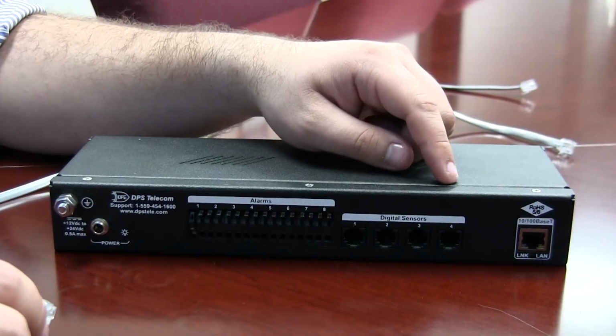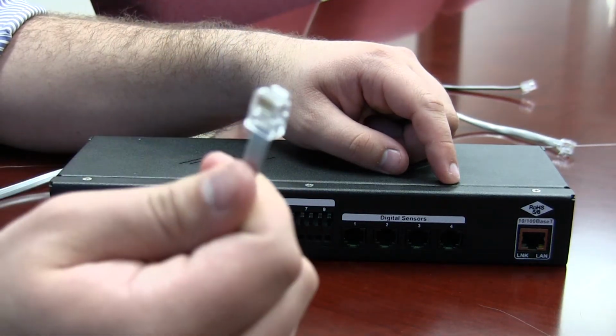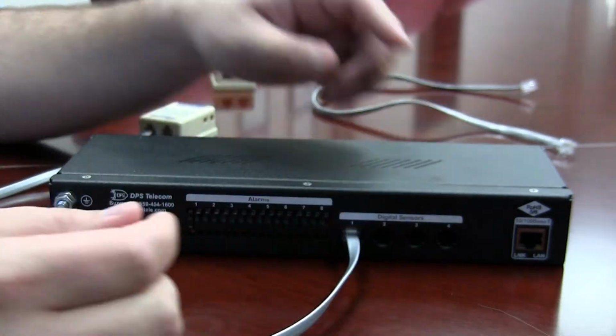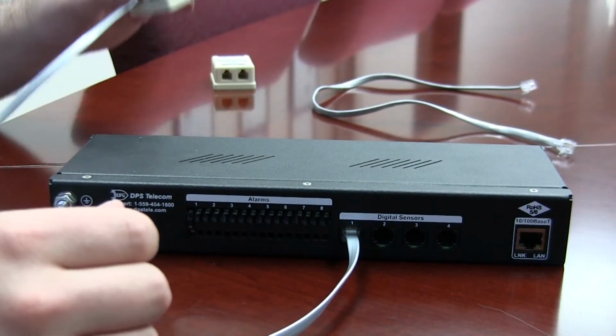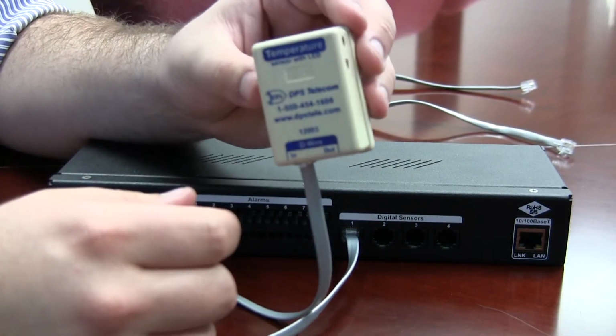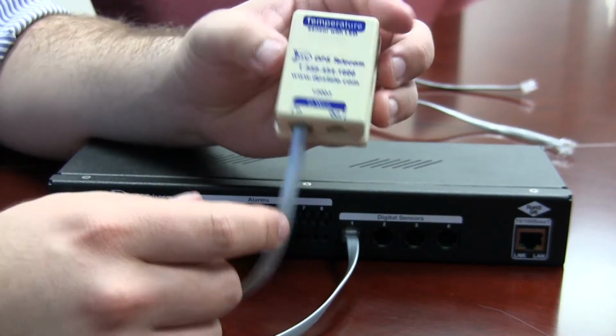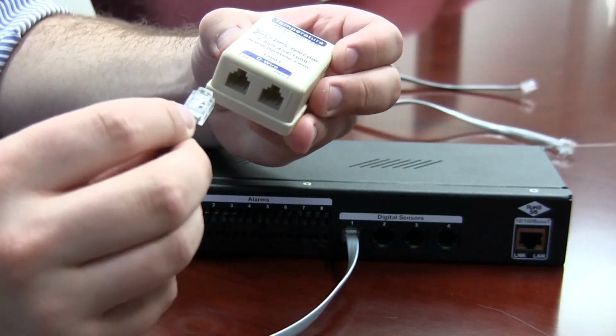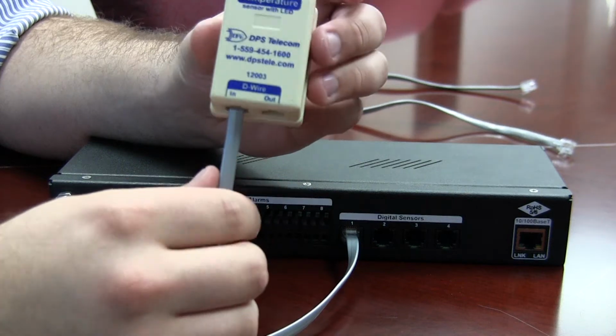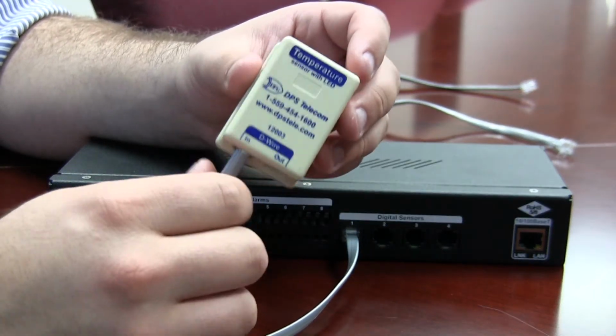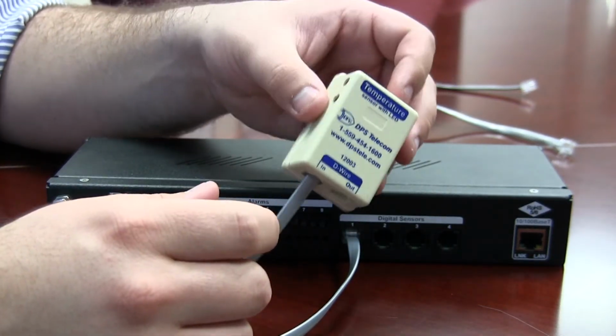To each of the four digital sensor inputs, you'll be able to insert a standard RJ11 cable that clicks in. This cable can be up to several hundred feet long, depending on how many sensors you're going to have in this string. And you're connecting to D-wire sensor nodes. And as you'll see, the RJ11 simply goes into the in port there. And this is auto-configuring, so you now have a temperature sensor that you can position wherever you need to at a critical location in your site.